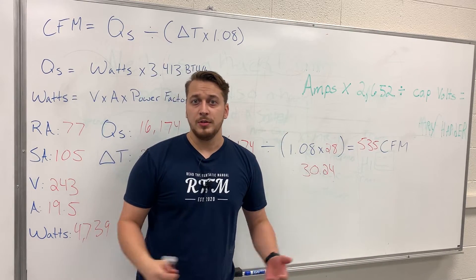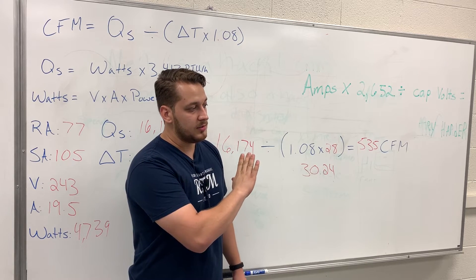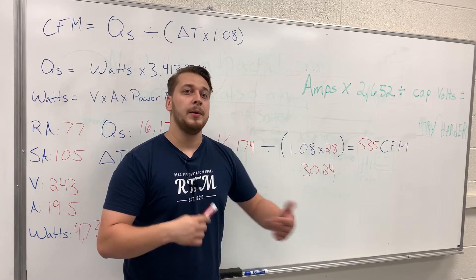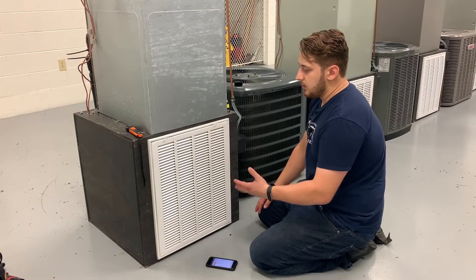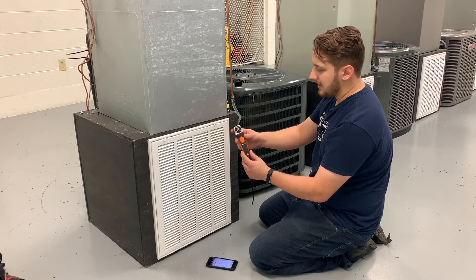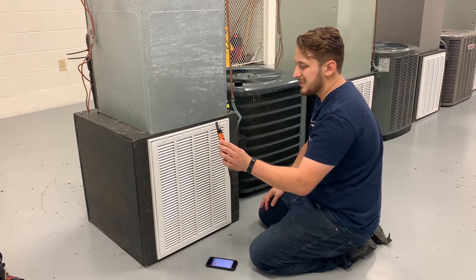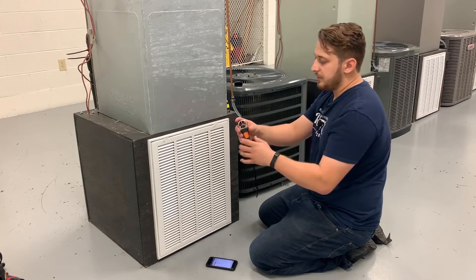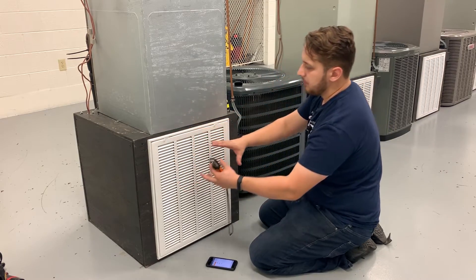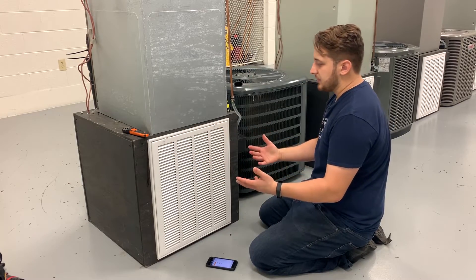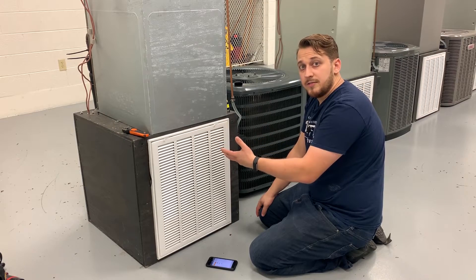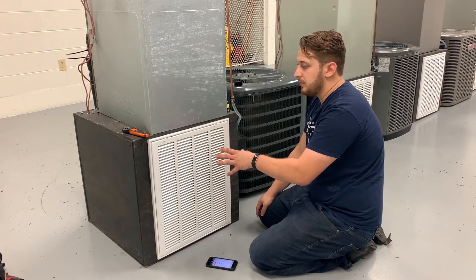Now we're going to traverse the return grill with a rotating vane anemometer and compare results. We're using the Testo 410i Bluetooth small vane anemometer. The larger the vane, the more accurate the reading, because it covers more surface area at one time. This exercise demonstrates how you'd use this method to solve for CFM.